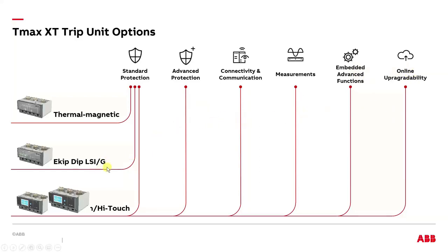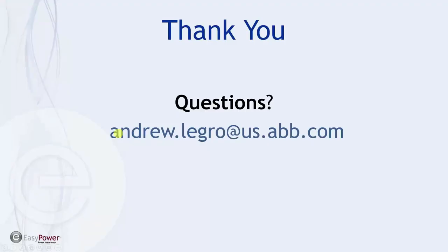What this slide doesn't convey correctly is that EKIP and the LSI solid state gives you more than standard protection, because this is LSI. I would consider standard protection to be thermomagnetic. So I'm going to change this and put another category here that says adjustable protection, LSI, because these two are definitely not the same. That was it. I had a lot of stuff to get through, so I had to rush a little bit. But I guess it's open to questions now.